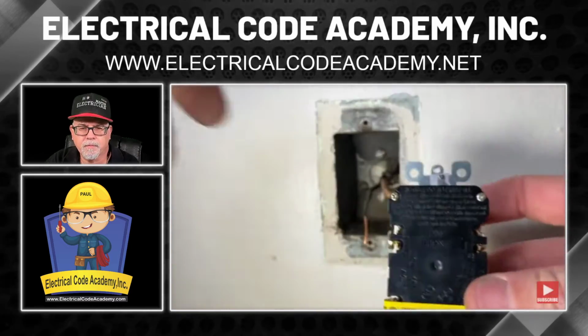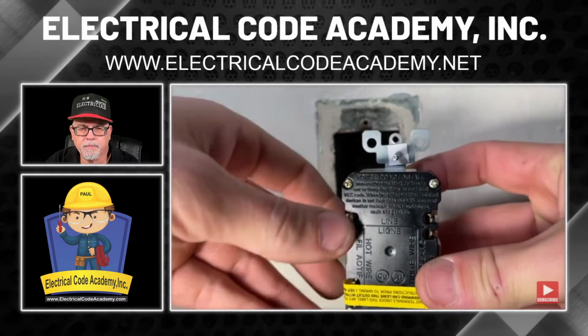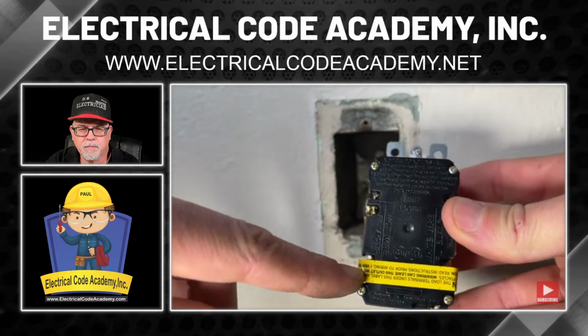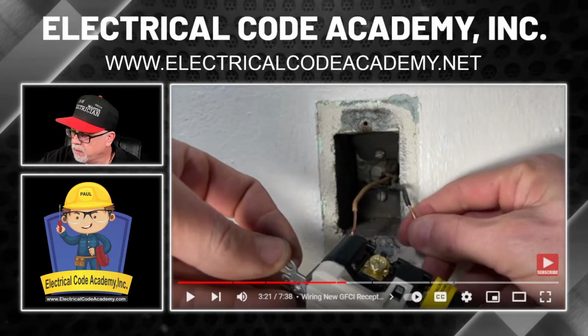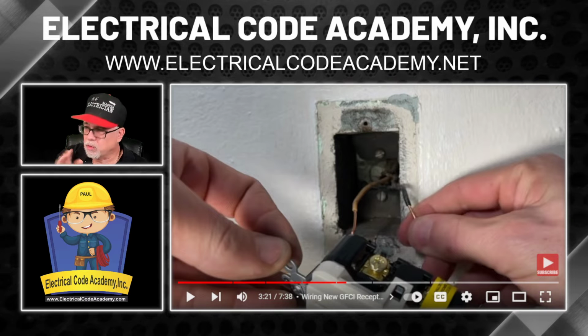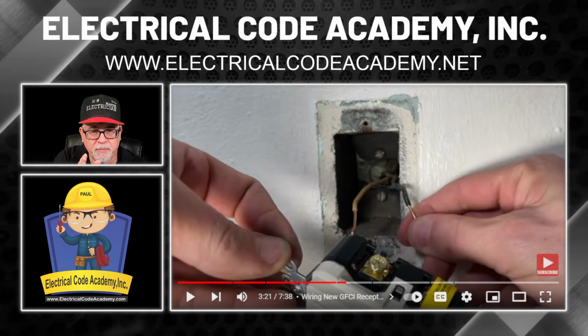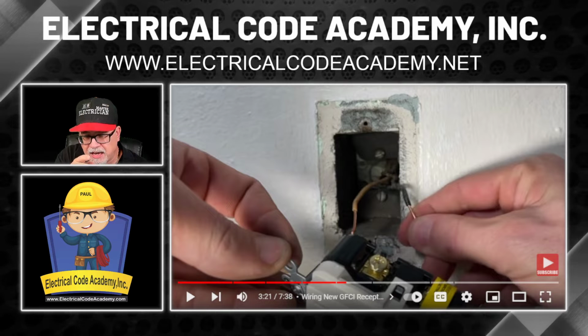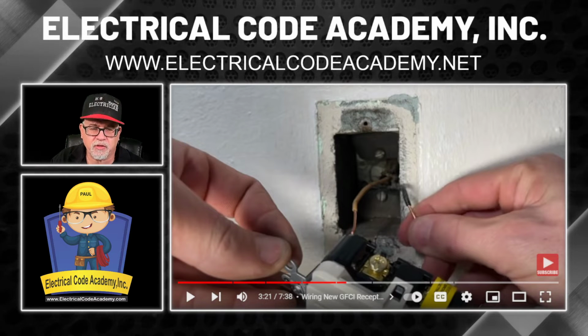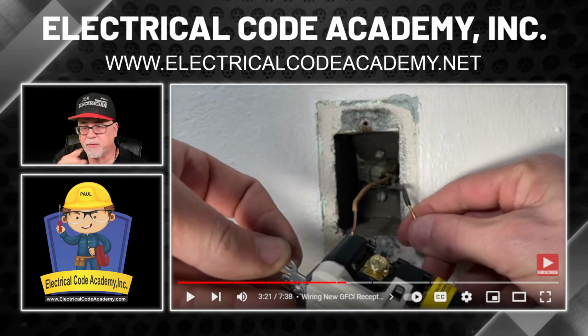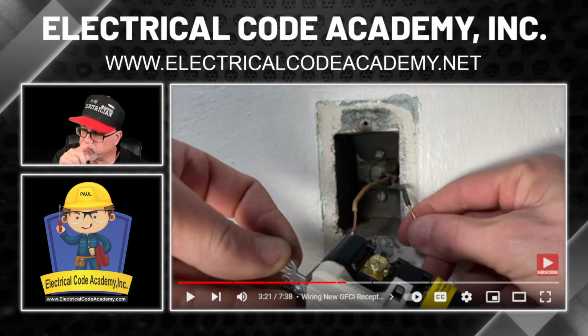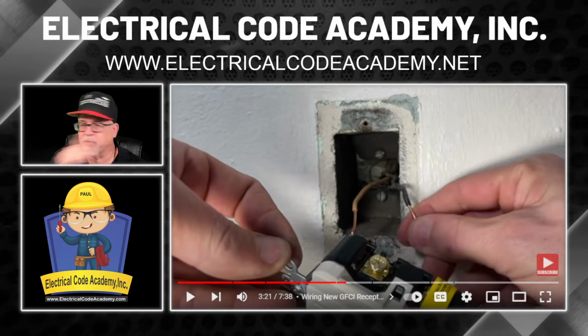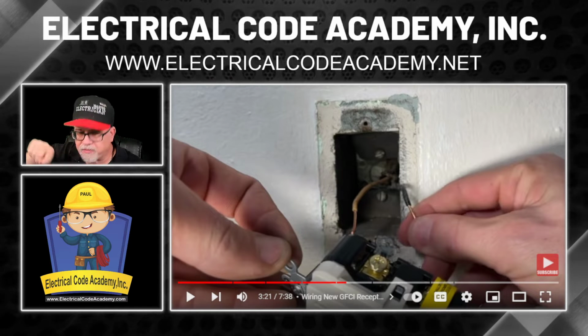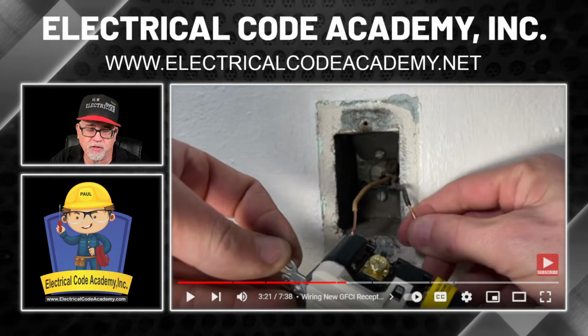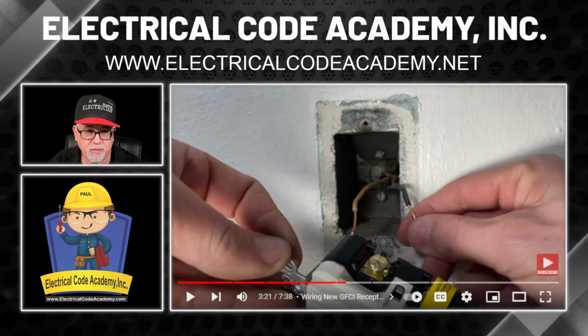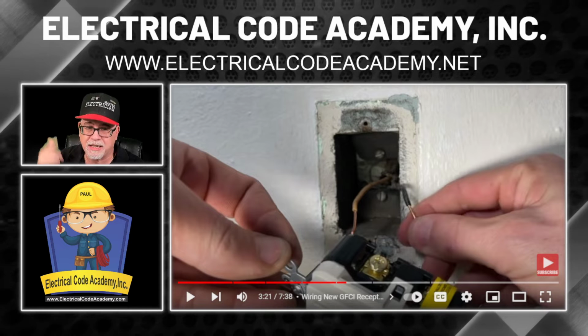Now you'll see we're only using the line portion of the GFCI. The load portions underneath this label for this instance will not be used. Now remember, if you're doing this, and we'll look at the code later, if this is the first receptacle and there was more than one cable in the box like he's got, if it was going to multiple receptacles downstream, then you would be doing the line in from the source and the load would be what's going out to the other receptacles downstream. So you're feeding into the device and then out of the device downstream. In this box, he's only got two wires. So it's either at the end of a loop or this was a branch circuit that's only one thing was run in this one. All right.